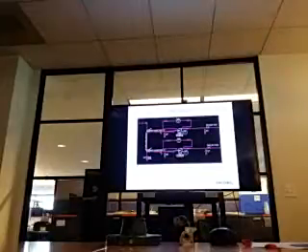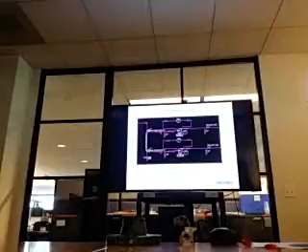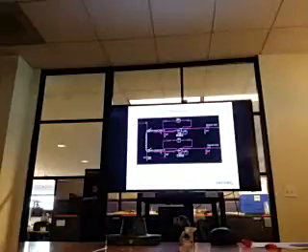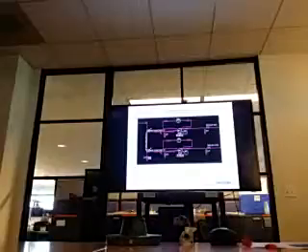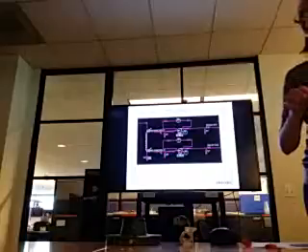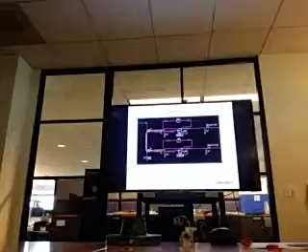So this is just ensuring that any live steam that's left in there is going to become condensate after that. That's why Fran and I are very adamant on our P&IDs that it's still considered steam through and including the trap and upstream. A lot of people like to argue with us. They say, "Oh, as soon as it leaves the steam main, it's condensate." I'm like, "No, it's not. We would like it to be." From a quality standpoint, that's one of the things we're trying to get into people's heads. And if you see those types of things too, and you can make that point, that's even better, you know, catch it early. So anyway, this is a thermodynamic steam trap.